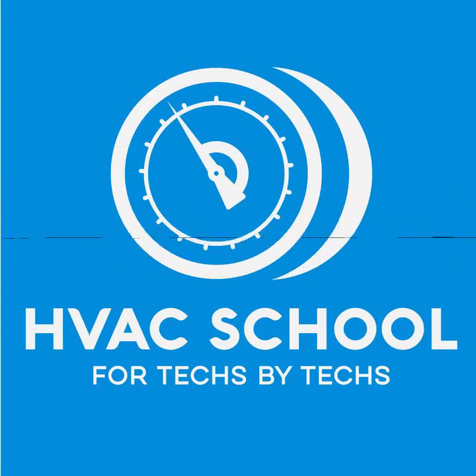This unit's not coming up, the display isn't on, so I know we have a power issue. I look inside and I can see we do have some power at the board, but I don't have the diagram out yet because I don't have the full panel off. So I go turn off what I think is the disconnect, because it appears to be the disconnect - it kind of goes down into the ground, and I couldn't tell for sure, but it was right there. I start pulling the panel off, and on these Hayward gas pool heaters, it's actually just a little side panel, and the thing starts arcing all over the place. Apparently I didn't have the correct breaker off, which in turn tripped another breaker, but it only tripped half of it. So I proceeded to continue testing, and then another wire popped off and started arcing some more. The problem was some loose connections, and I made a fool of myself in front of my son.